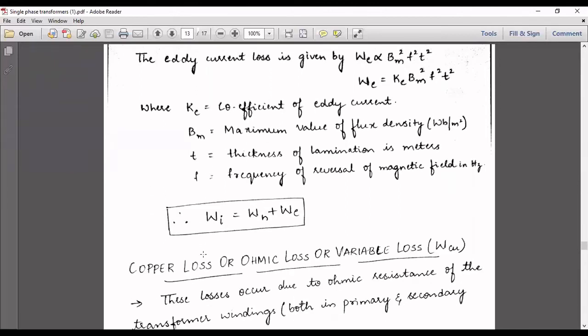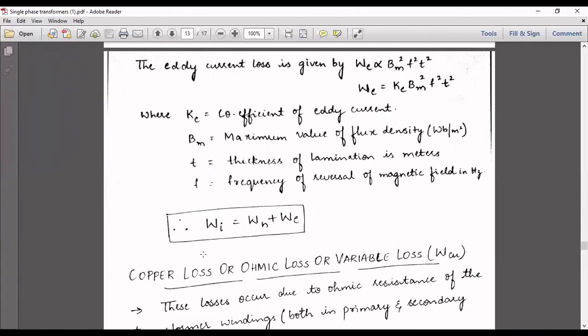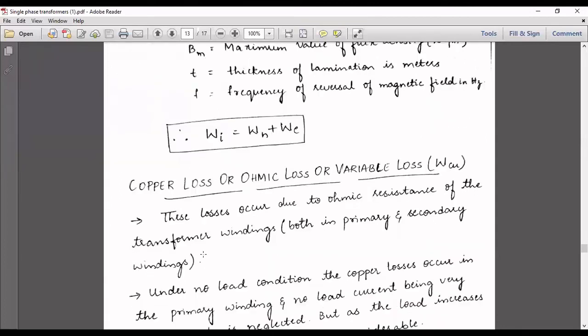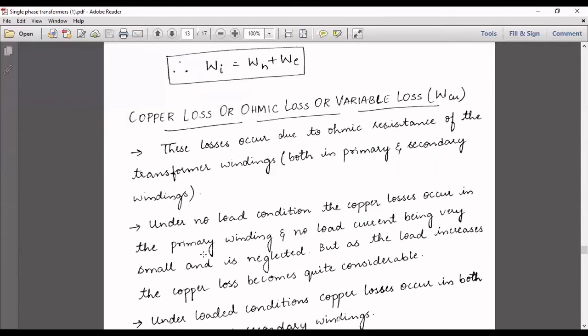Therefore, the iron loss is given by the sum of hysteresis loss plus eddy current loss. The material taken to make the core always remains the same. Once the material is fixed, the core losses also will be fixed. They do not change. Therefore, these core losses or iron losses are also known as the constant losses. And the second loss is copper loss, or the ohmic loss, or the variable loss.